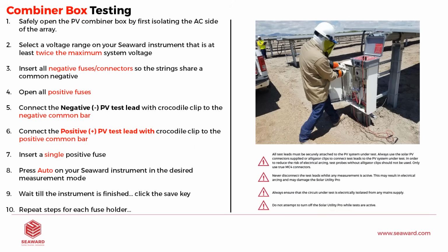So generally, when we're dealing with these larger systems, we're going to be operating inside of the combiner box. And I'd like to describe the process for you for working inside the combiner box. So first of all, we've got all of our arc flash protection to the correct rating. We have the area clear from our work colleagues who are not in the test area. When we open up the box, we safely isolate the box, we open it up. And the first thing I want you to do when you open that box is just take a look at it. Okay, do a visual inspection of the combiner box. Make sure there's no faulty connections in there. Also, maybe smell, okay, because we can smell arc faults inside of the box. And even I've seen, I'm sure you guys have too, spiders in boxes or small mammals. So just make sure the box is free from obstruction and visually it looks okay.